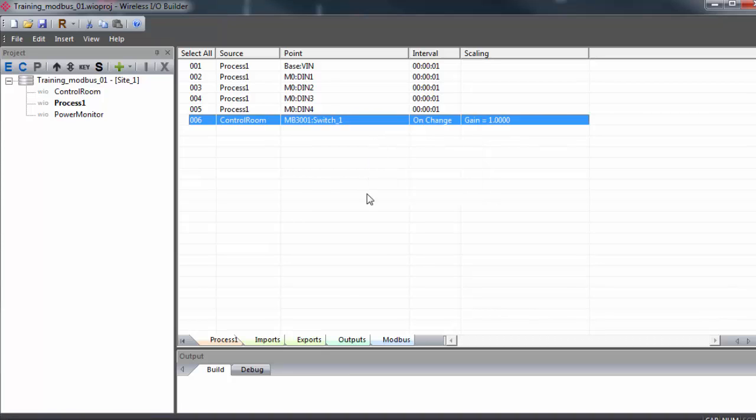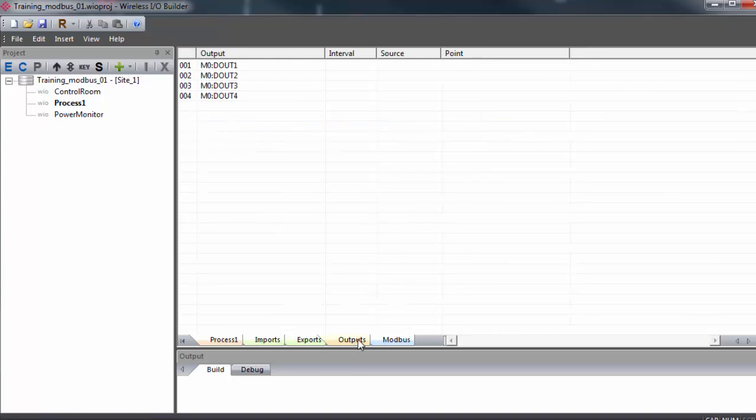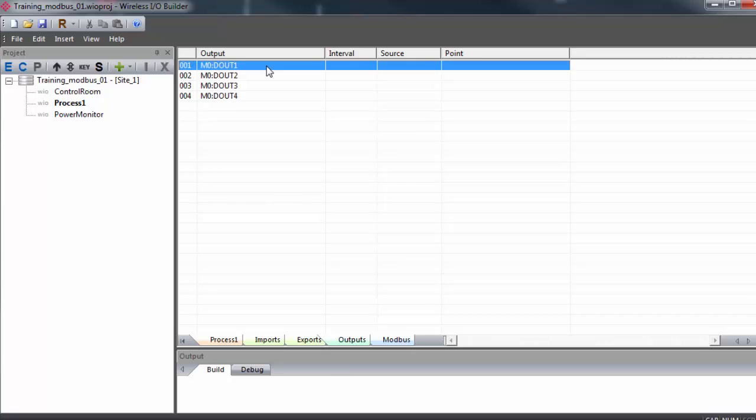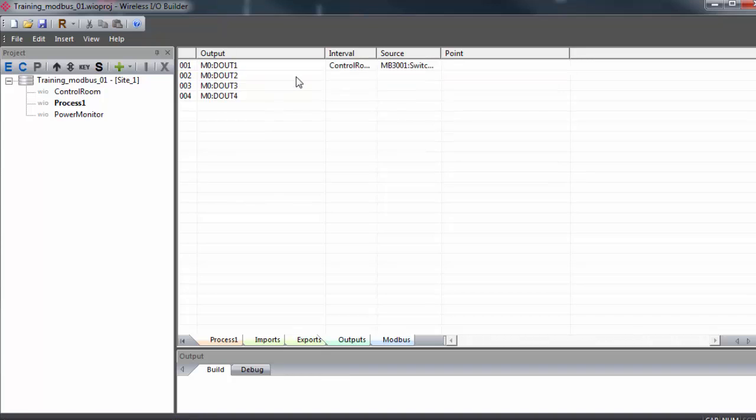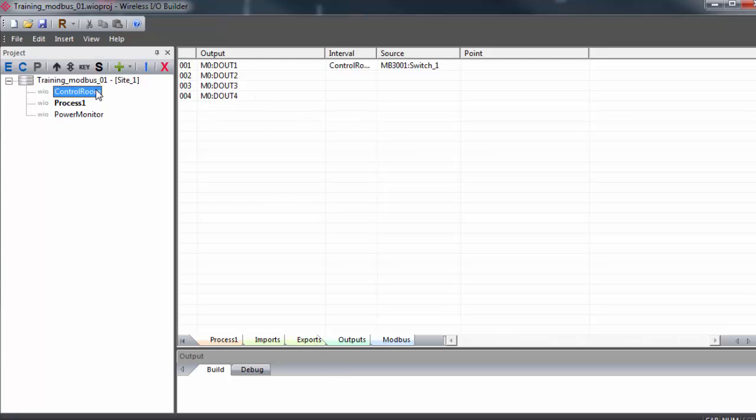Go to the output tab. Select the digital output 1. Right click and select paste output source. Now when the Modbus Master writes a 1 or 0 to register 3001 on the control room gateway, it will drive the output on process 1 on and off.